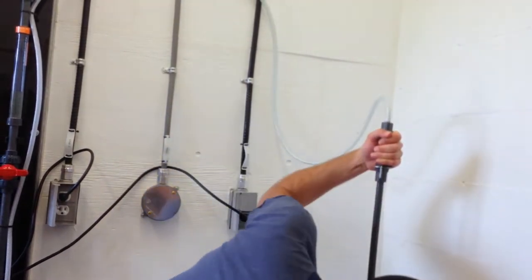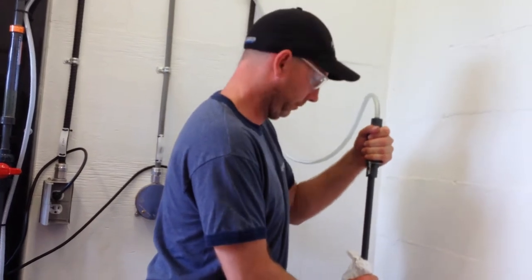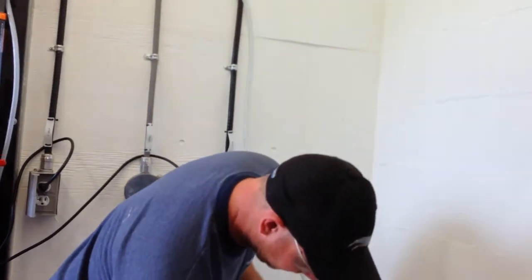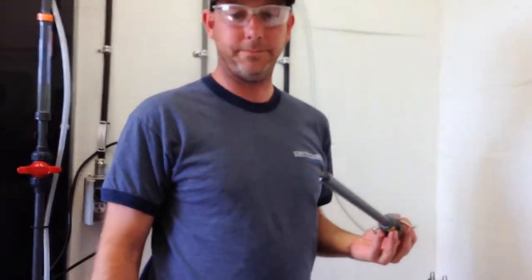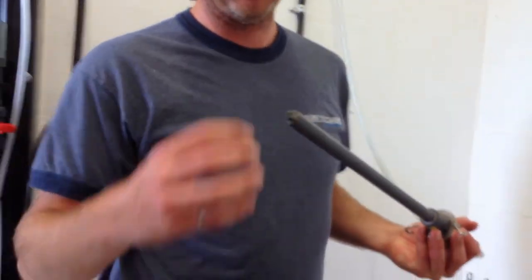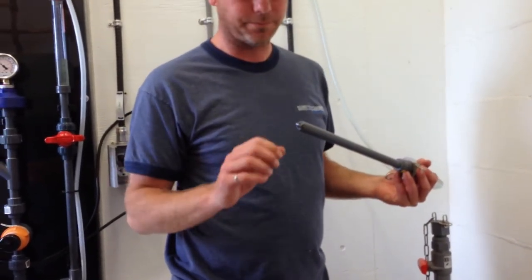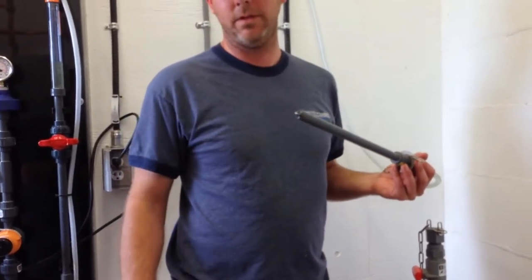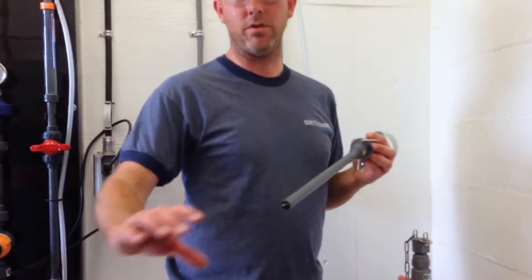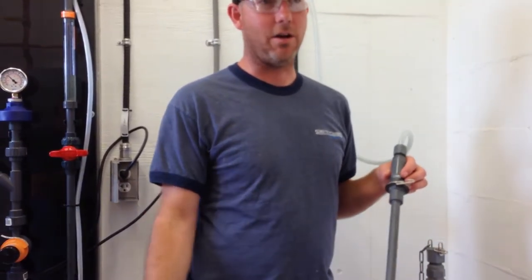Okay. And if we're smart, that's your duck bill. So what you want to do is, there's a very small slim line right in it. You start checking for white crystallization around it. There's going to be a little bit of bleach on it; you're just looking for crystallization. And if you do find it, it wouldn't be a bad idea to have a backup. You can get basically just this piece as a set, and then you can soak this guy in something like CLR.